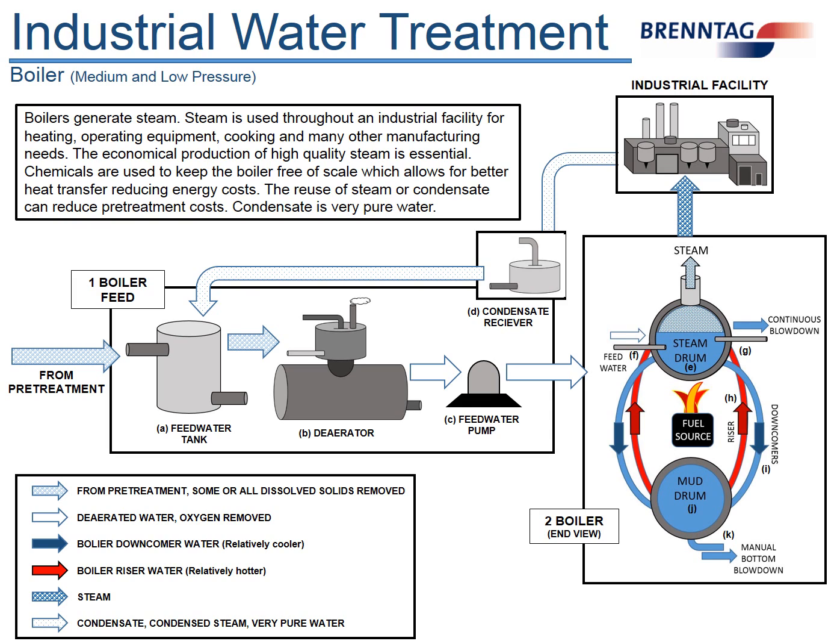In a boiler, we have a circulation that starts to occur. Water that is closest to the heat source rises to the top, where it is boiled off and generates steam to a facility. The cooler water, which is further from the heat, circulates down through what's called the mud drum, and we start to get a circular motion within the boiler. Typically, what will happen is it comes up through the risers and then down through the downcomers.